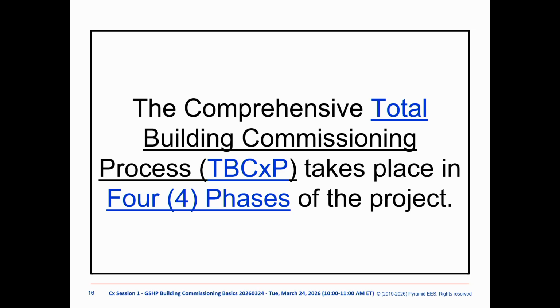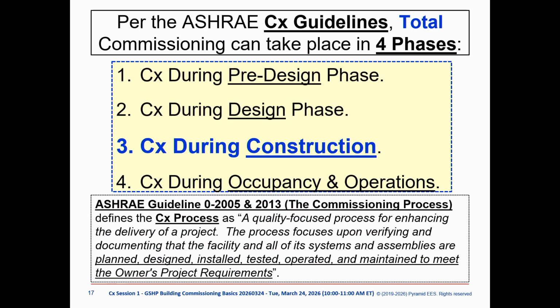Here are the four phases: pre-design, basically when the owner and a candidate consulting firm are getting together, we need to think about that. During design itself, the 30% CDs, 60%, 90%, 100%—CDs are construction documents—are checked against the commissioning process because there are design reviews. When you do design reviews as the commissioning agent, you can tell everybody on the team, this is what we will be testing in the future, so you incorporate commissioning here.